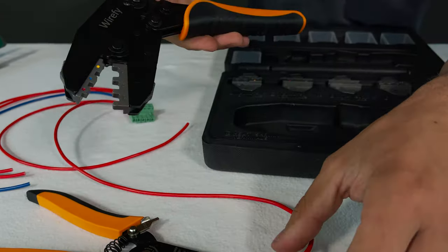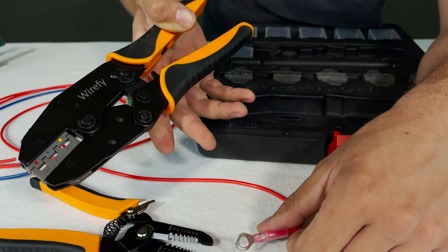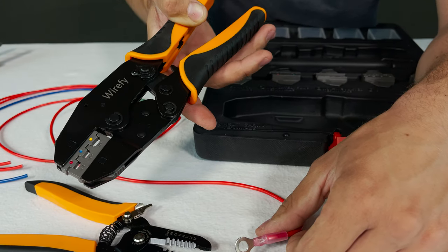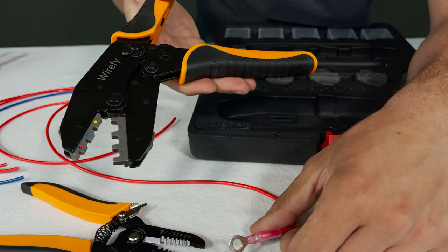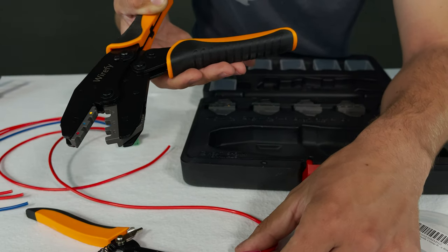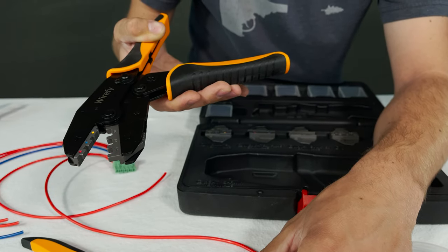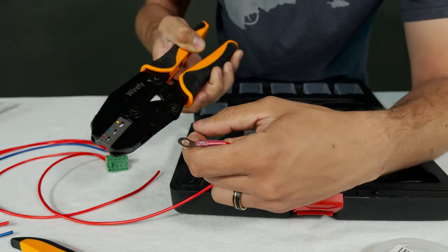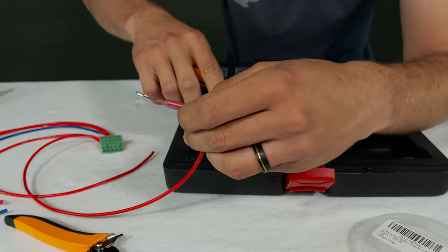Now this is a ratcheting type so if I stopped halfway it'd be stuck. You'd have to continue squeezing in order for it to release. So this tool is nice because it makes sure that you don't under crimp your connectors as long as you use the correct setting based on the color of your terminal.